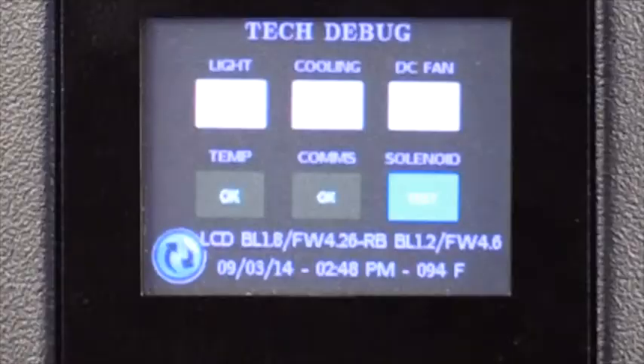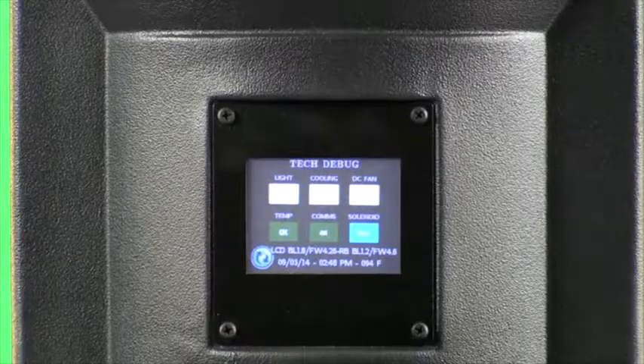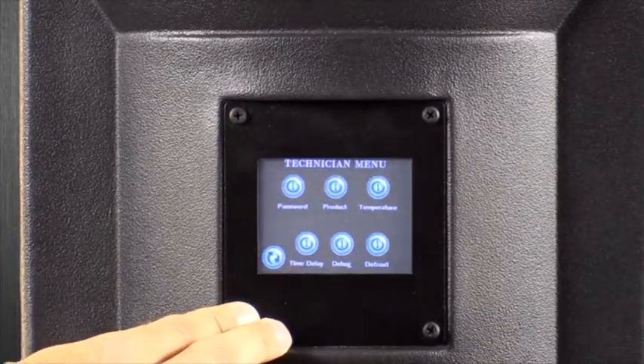Also listed at the bottom of the Tech Debug menu, you will see a series of numbers and letters. This is the current software version that is programmed into every unit. Also listed directly below that will be the program date and time, along with a secondary temperature reading. That is the reading of the temperature of the main capillary compressor line that is located on the inside of the left access cover.